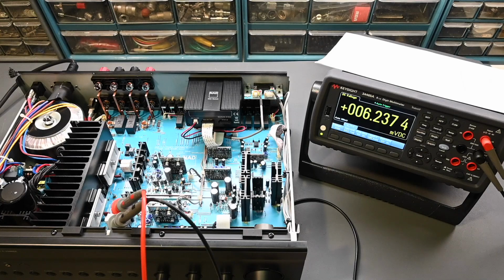But if you're in a location where you have considerable line voltage variations and you're trying to do this adjustment, you might notice that the values are kind of hunting around considerably and you can't get it to stabilize. You might consider using a variac to stabilize the line, but use it within reason. If it's just a few volts up and down on the line, probably not a big deal, but if it's wide variations, it might help out. But again, if you're using it to try and correct for just a little volt here and a couple volts there, you're going to be there all day making adjustments and just going in circles. It can be very frustrating. So I wouldn't recommend it in most cases, but again, it might help out if the line is varying considerably.